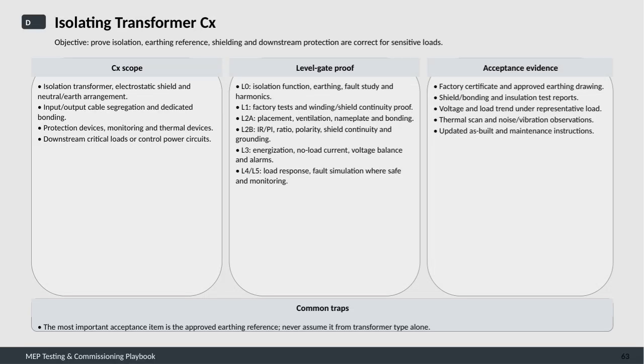On this slide, we focus on isolating transformer commissioning, which is crucial for protecting sensitive loads. The main objective here is to verify proper isolation, ensure the correct earthing reference, confirm shielding effectiveness, and check downstream protections. The commissioning scope includes several key components.